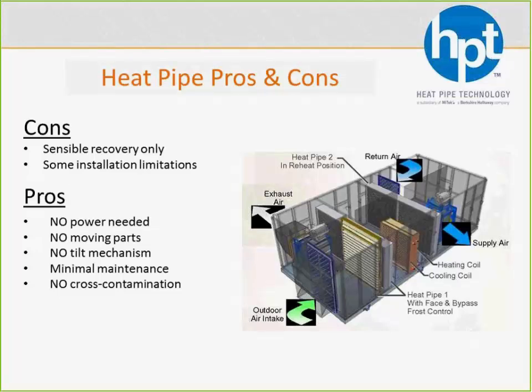Another big advantage to the heat pipe is that we don't have any cross-contamination. We're not going to carry any air from one airstream to the next. So when you're comparing us to, let's say, an energy wheel that does have more effectiveness than we do, if it's a scenario where cross-contamination is a concern, it's not even an option where we would be.